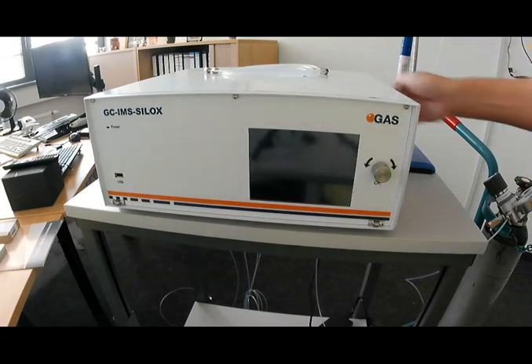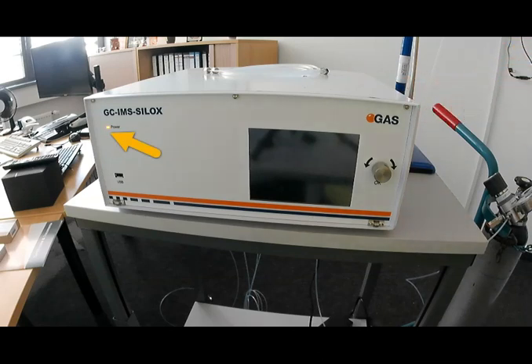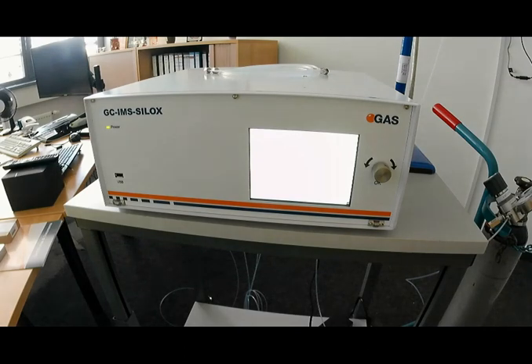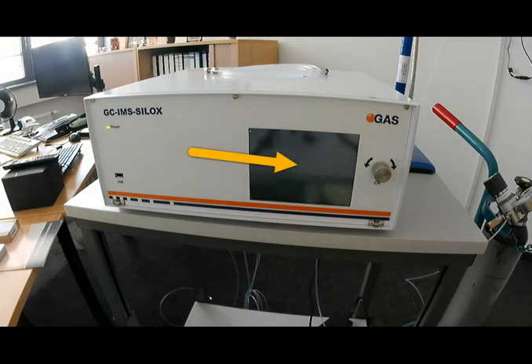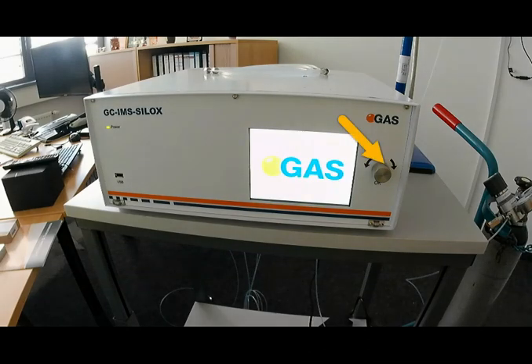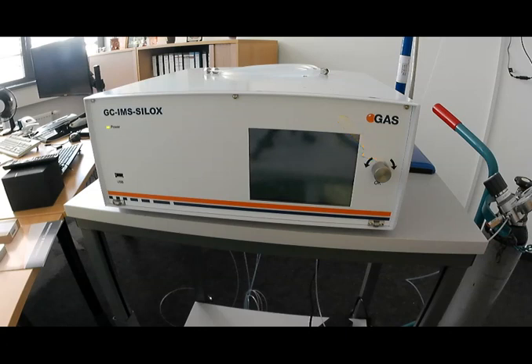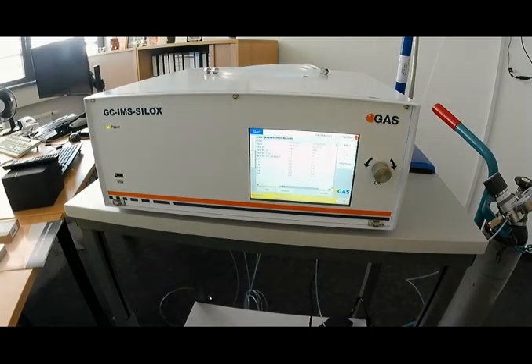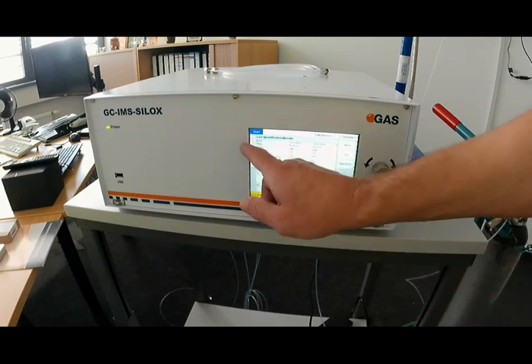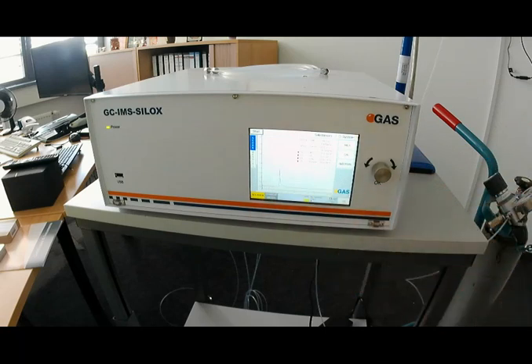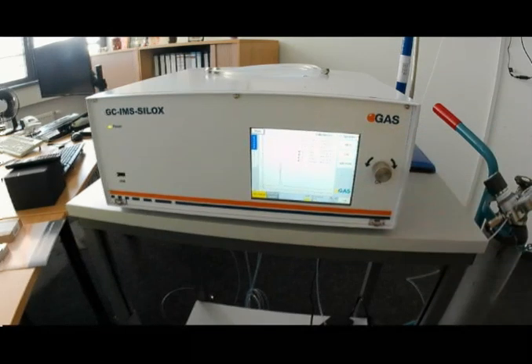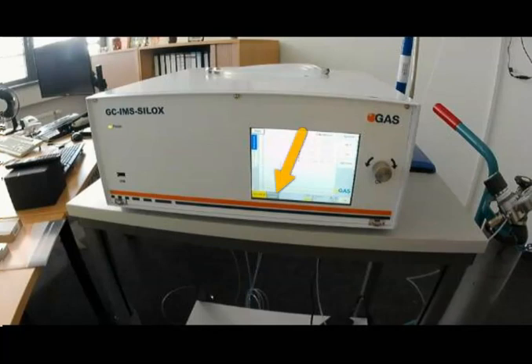This is the front panel of the GC IMS SILOX instrument. After switching on, the power LED is turning green and the instrument screen will show various phases of the boot sequence, including showing the gas logo. There is a rotary knob which we can use, or we can use the touch screen once the firmware is fully loaded. It is possible to switch between different tabs. We have seen the result tabs of the start screen, and the scope tab shows the raising temperatures of the instrument during the warm-up phase. It's the so-called startup phase, and we also see a raising reaction ion peak in the middle.